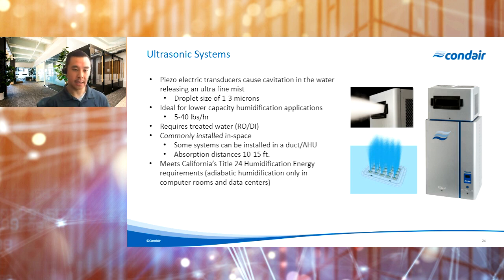Now, in terms of design considerations or use of these types of systems, the thing to keep in mind here is these are typically smaller capacity systems, with outputs ranging in the 5 to 40 pounds an hour range. So for that reason, we typically see ultrasonic systems as a more cost-effective way to humidify data centers, small data centers or small computer rooms. Just to give you an idea, a typical 40 pound an hour ultrasonic unit would consume just under a kilowatt of electricity. And that would be a system with an integrated fan blower like you see in the picture here. These systems are typically installed directly into the space with the blower pack.